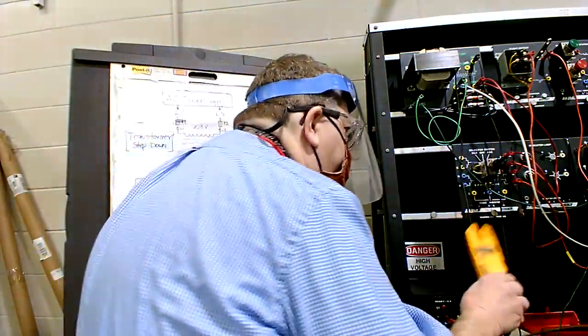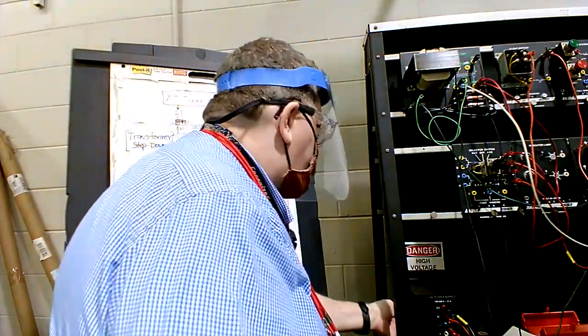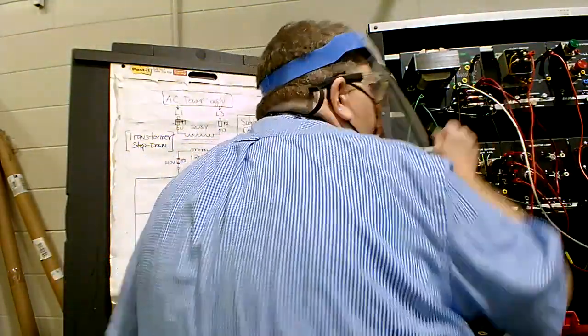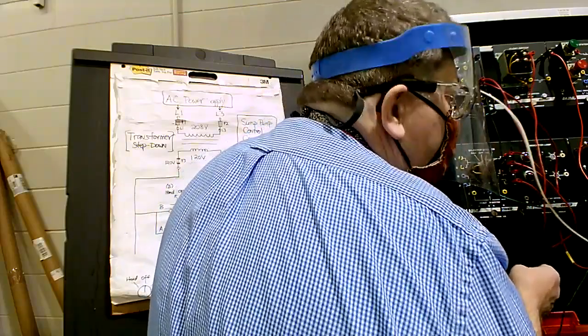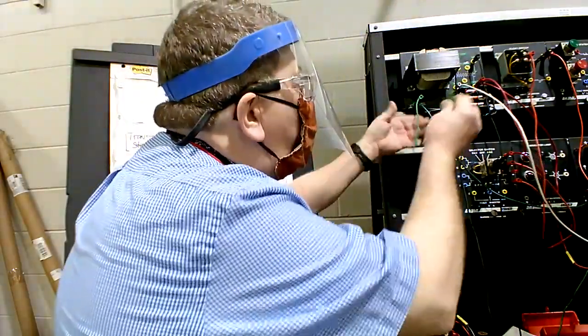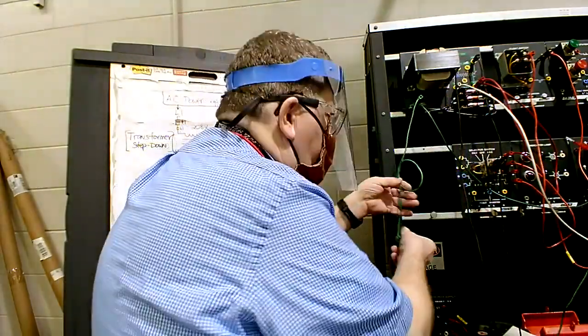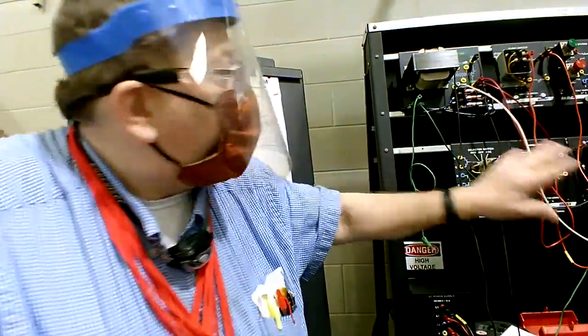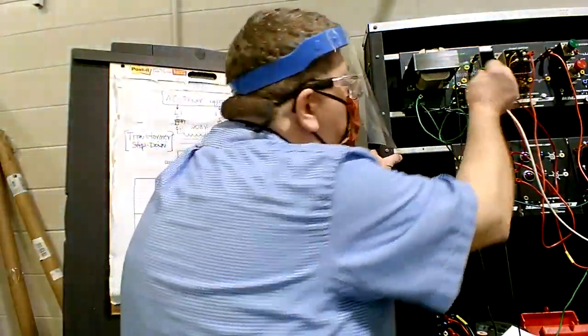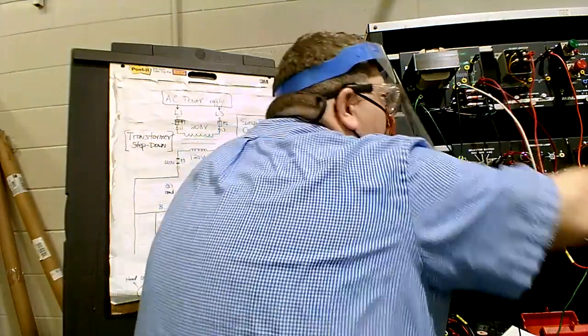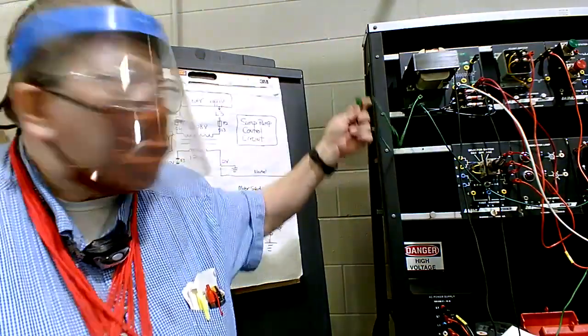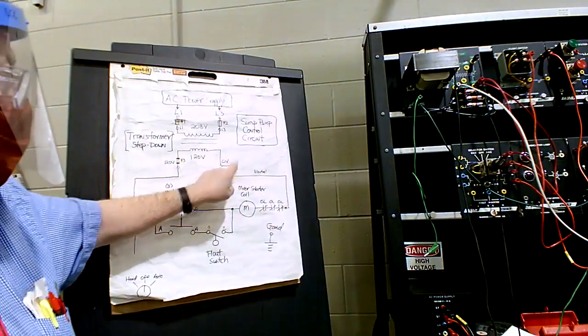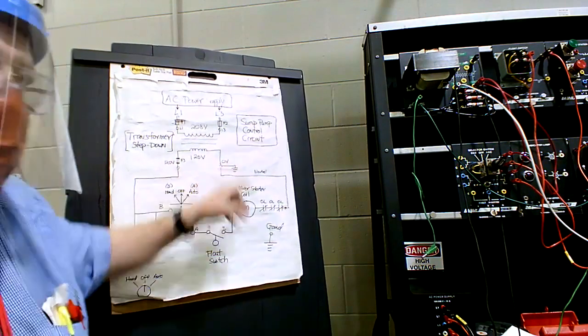Now watch what happens here. Cut your float off. You have to have neutral going back there. What we're doing is removing the ground jumper from neutral. We're not going to ground neutral. Look, everybody watch. We've taken that ground jumper that was on neutral and removed it. So neutral is still there, but it's not grounded. That's called floating. You have a floating neutral, a floating secondary that's not grounded. It's still 120 volts, but neutral and ground are not together. They're not bonded. Now let's cut it on and see what happens.